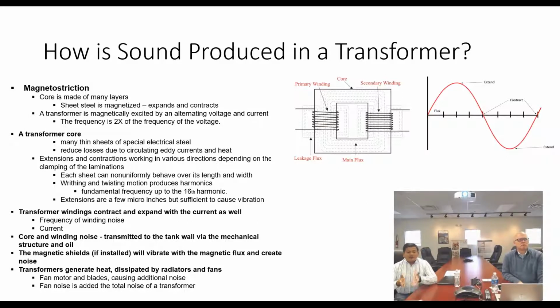Right? The transformer core is made from thin laminations, or thin sheets, of specially electrical grade steel. I'll explain that sheet in later slides, but right now I can say that those sheets are called CRGO, cold rolled grain oriented steel, and they have a silicon coating on top and bottom, on both sides of the steel lamination. It is made this way to reduce the losses due to circulating currents, eddy currents, and subsequently the heating effect of the core.